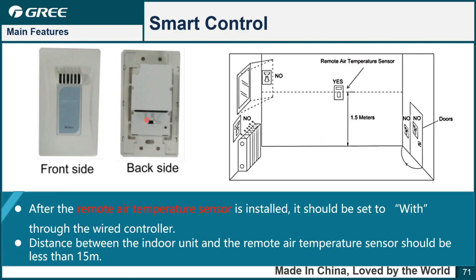And this is the remote temperature sensor for the room. For example, if the customer wants to use a temperature detection point in the room, they can choose this one and put it in the room around 1.5 meters at this height, and the default, standard length of the remote air temperature sensor is 15 meters.